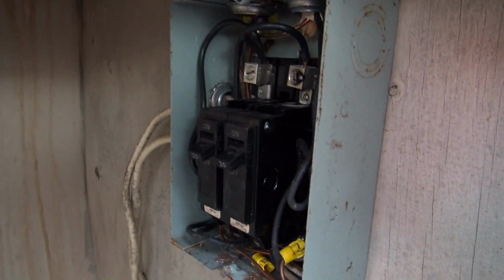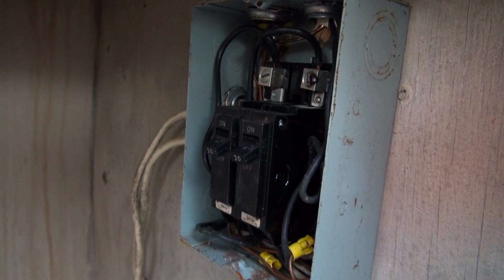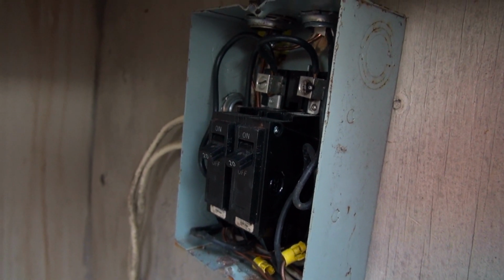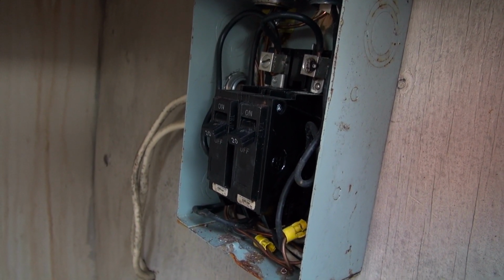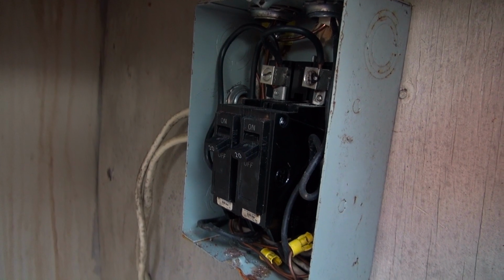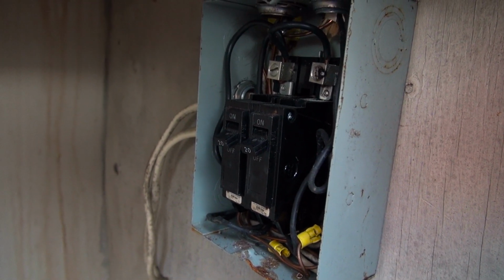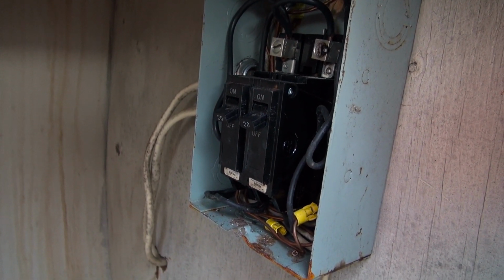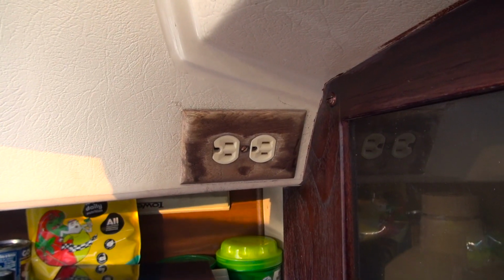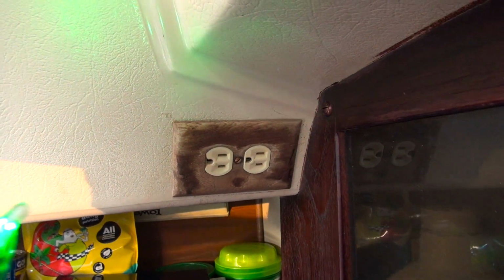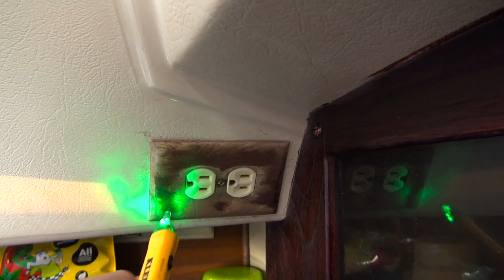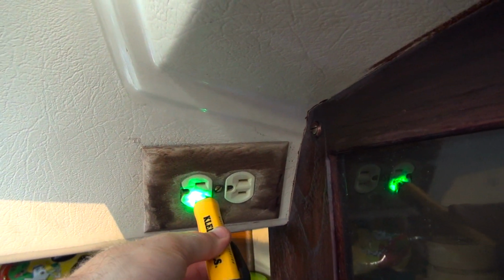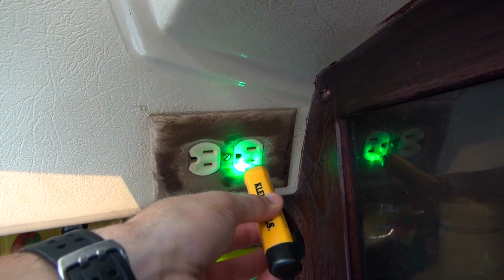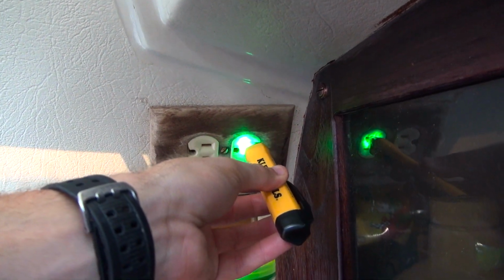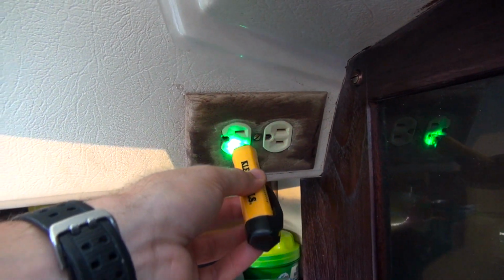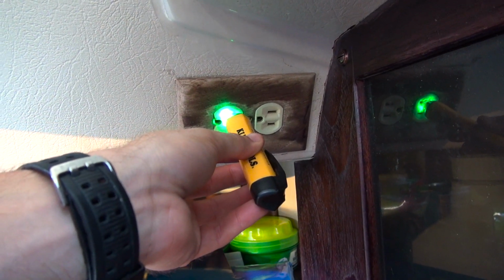This means the electrical problem is not with the marine power receptacle, and not with the circuit breakers, so that leaves one culprit: the AC outlet. Using the same voltage tester, I can fit it inside the openings, and you can see that even with all the breakers flipped on, this outlet does not work.